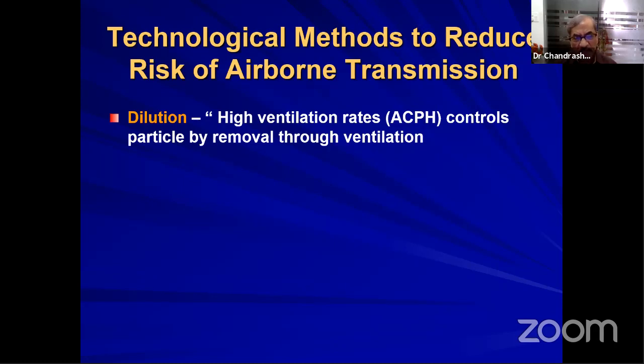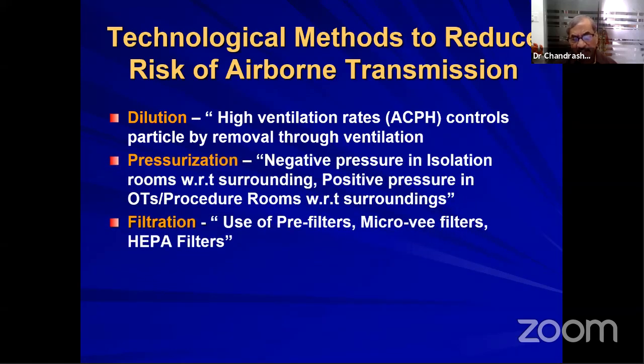We even have a record that when SARS hit the country in the past, cross-ventilated wards never had any problem, and all the centrally air-conditioned people had all the challenges. So this is one of the important things, how you can maintain the air changes. And pressurization, anyway, you are aware that we maintain negative pressure in the isolation room. And filtration, use of pre-filter, micro-vee filter or HEPA filter.